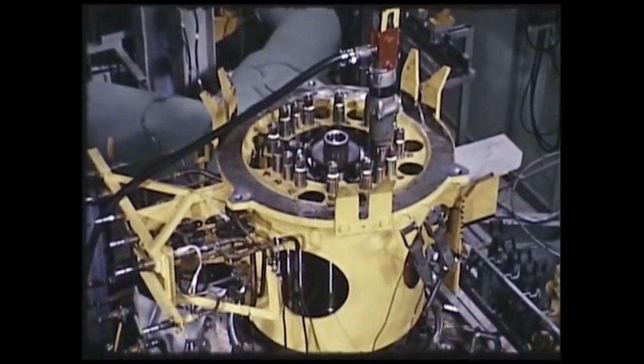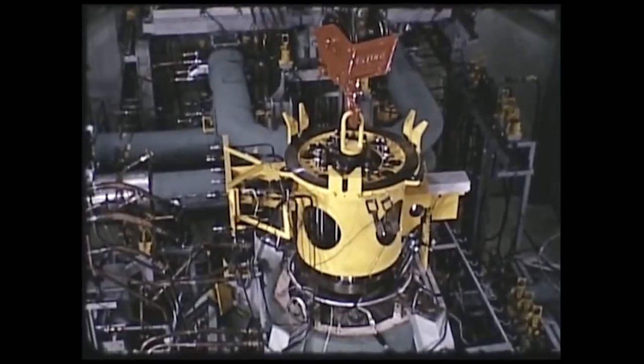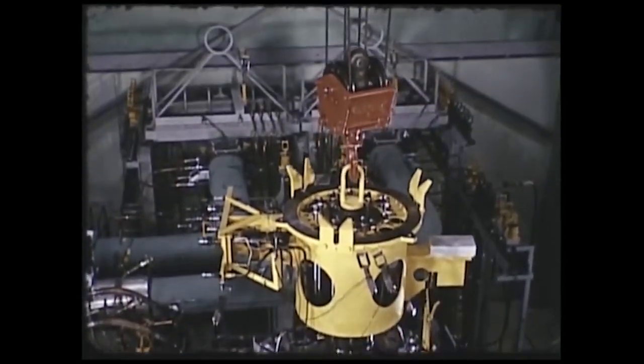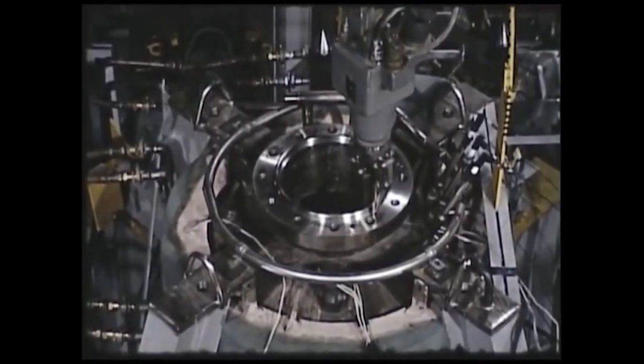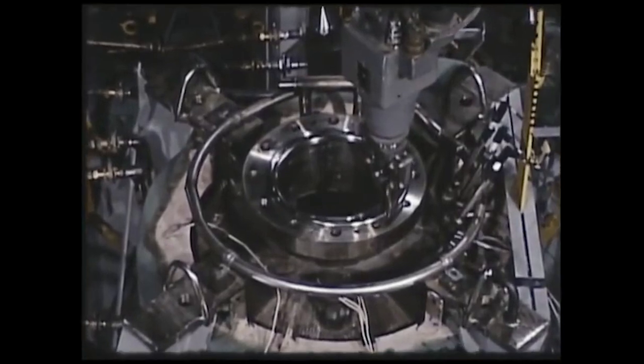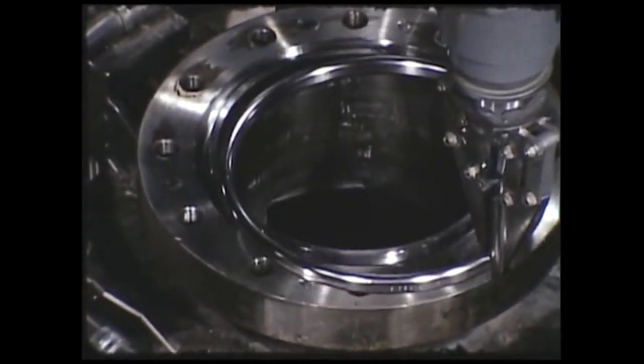Four jack bolts are actuated to break loose the seals between the pump rotary and stationary elements. An eye bolt is inserted in the pump shaft to facilitate its removal by the crane. The pump flange O-ring gasket is the final piece of equipment removed in this setup. Total time for removal of the motor and pump, six hours.